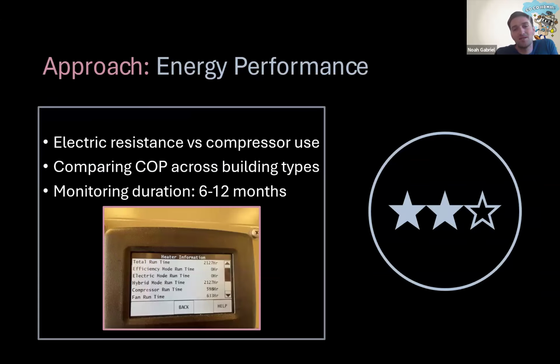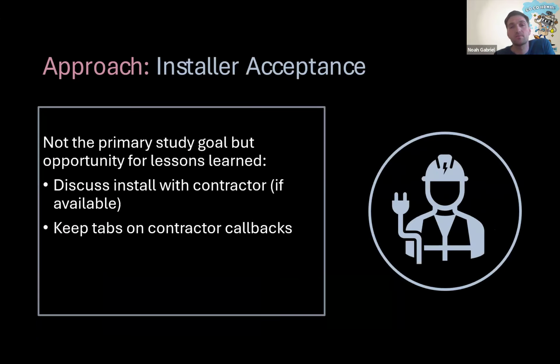Basically for energy, we're looking at COP. We're doing M&V for 6 to 12 months depending on the site, so it'll be a good chunk of data across a variety of seasons. We wanted to pay special attention to how much electric resistance is being used versus the compressor, because if it's only electric resistance, you're going to cap out that efficiency at around 100% and not get the most out of your heat pump. So we want to make sure it's mostly compressor use.